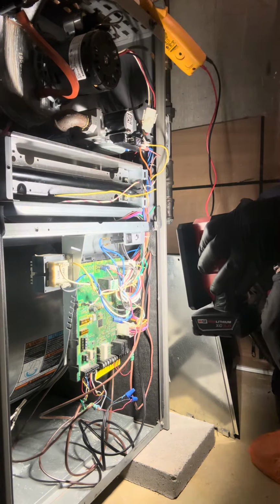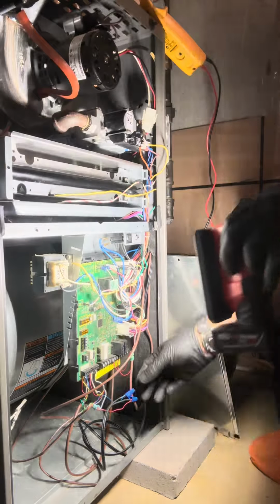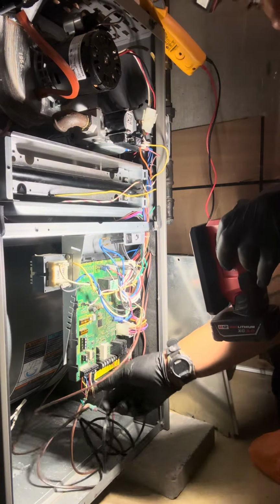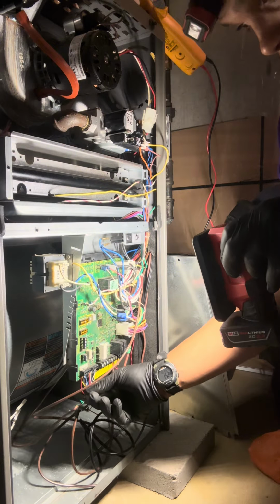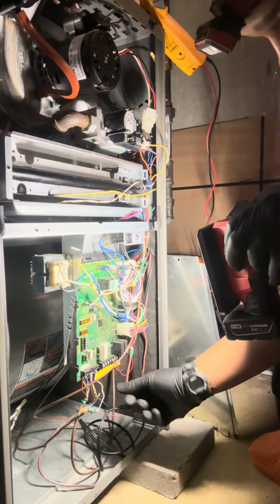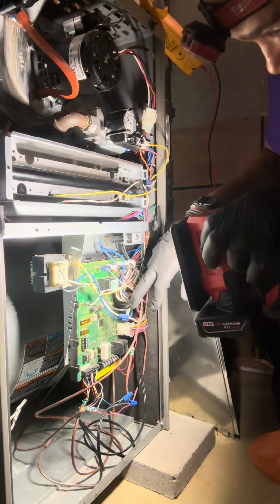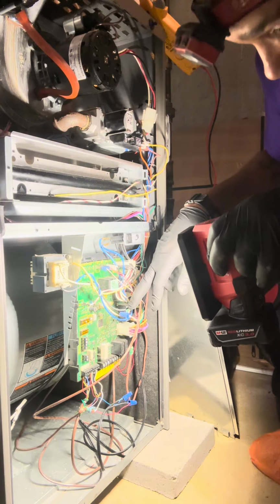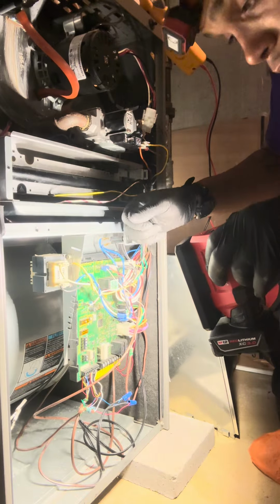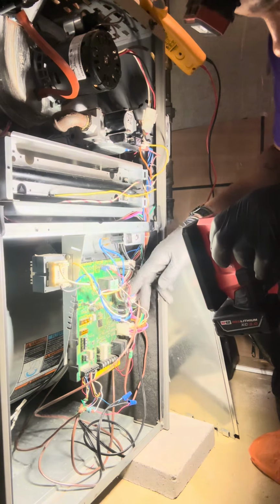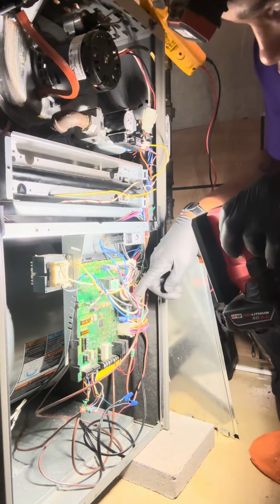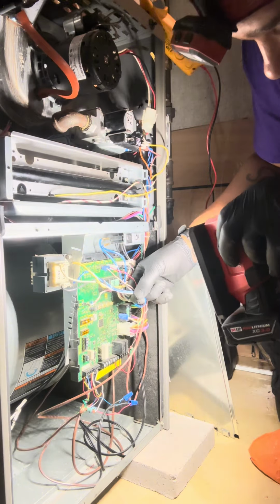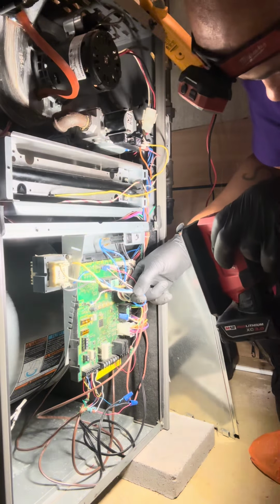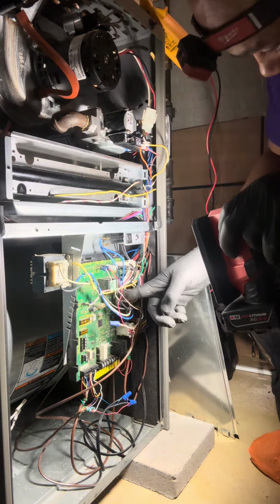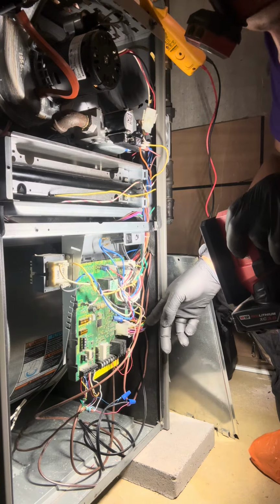So every time you pull this off, I want to check and make sure all the wires are secure. I just tug on these wires, make sure nothing's loose, all the connections are straight. I want to check this board and make sure I don't see any arcing marks, like any black arc marks from electrical overcurrent situations. But this board seems to still be in good condition.